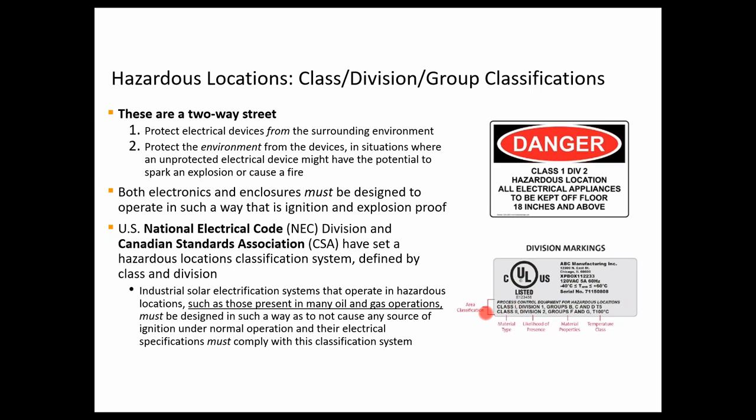A common misconception is that the mark from the listing agency needs to be a UL mark — that's simply not true. Any NRTL, any nationally recognized testing laboratory, can certify the product to these classification standards. For example, we use Intertek for our SunSaver certification, and you'll see a different marking than UL on the terminal cover. The key when examining components is to locate the specific class, division, and group markings to understand where they can be sited within a gas and oil site.